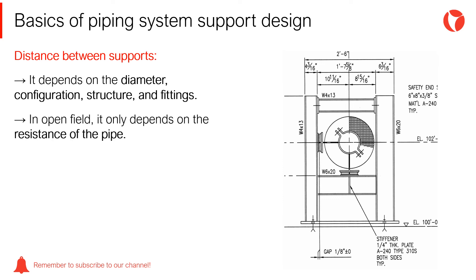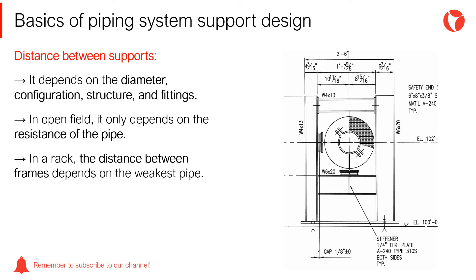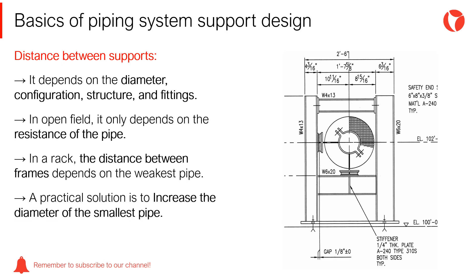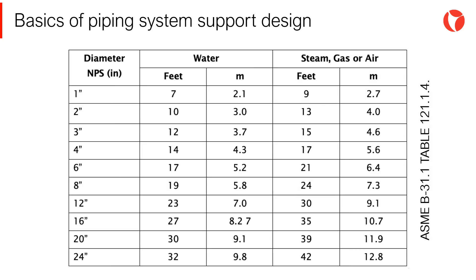In a horizontal simple open field pipeline, the spacing of supports depends only on the strength of the pipe material. The distance between frames of a pipe rack is determined based on the weakest point. Sometimes the most practical solution is to simply increase the diameter of the pipe to the point where it is self-supporting throughout the required span. The maximum recommended space between supports can be established by two methods: through the calculation of the stiffness of the pipe according to the stress and allowable deflection, and through tables in codes, project specifications, or client specifications, as shown on the screen.